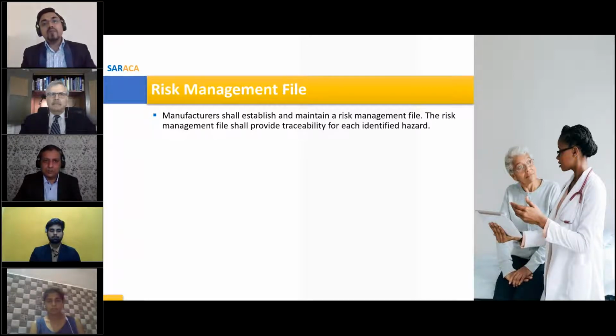There are many hazards you may face during your medical device use or from post-market surveillance activities, so it's very difficult to trace all those hazards. If you put all that documentation in one document or one file, it will be really helpful for you to trace all those identified hazards which were associated with, or which had happened in, your earlier medical device in your earlier phase, which you get from your post-market surveillance or any complaints process.